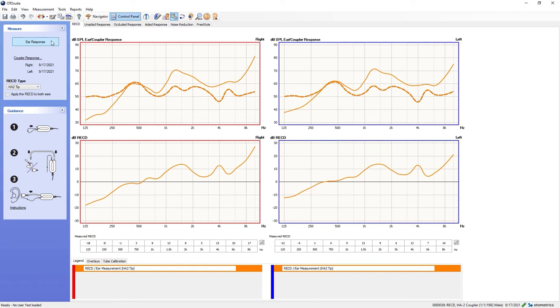The dashed line in the top graph is the coupler response. The solid line is the ear response. The RECD is only displayed in the bottom graph after the ear response and coupler response have been measured. The RECD is calculated as ear response minus coupler response. RECD values are calculated and displayed graphically for 1/3 octave frequencies. The measured RECD table below the graphs displays the RECD values for the frequencies from 125 to 8,000 Hz.